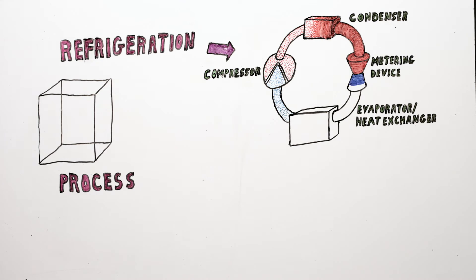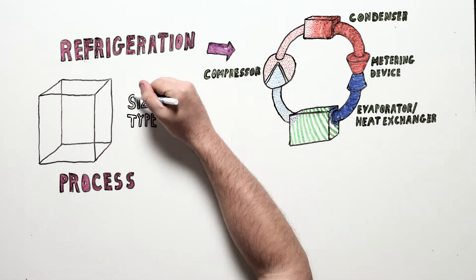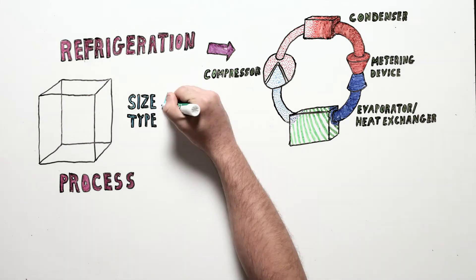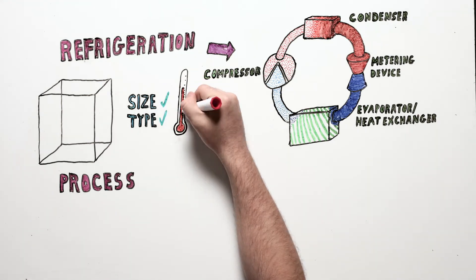The metering device reduces and regulates the pressure of the liquid refrigerant. The evaporator or heat exchanger takes advantage of the lower pressure and lower evaporation temperature to remove heat from the process fluid. Each of these components is selected by size and type to work efficiently to remove the amount of heat being produced and at the temperature required by the application.